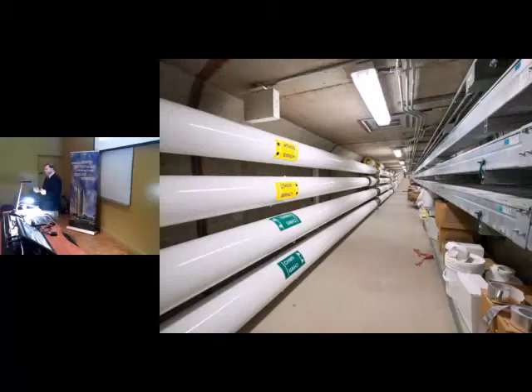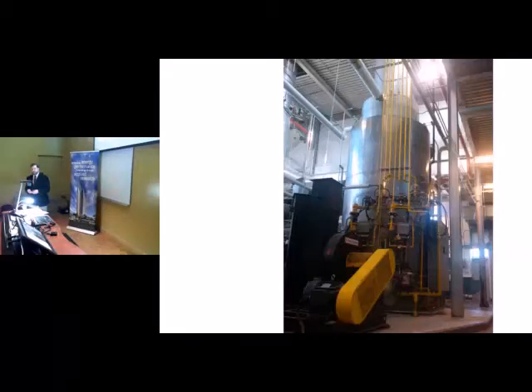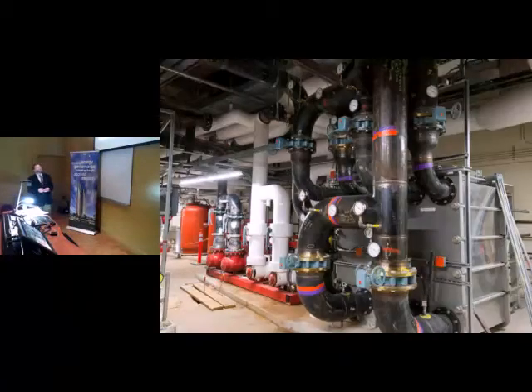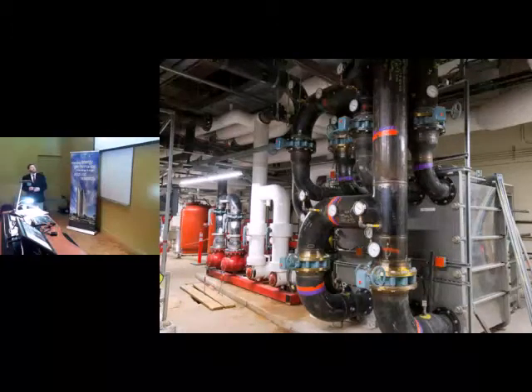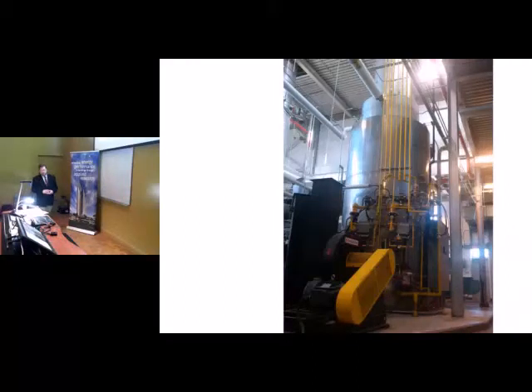We then take the water in the powerhouse and run it through an additional energy efficiency device, which is this device here. This is some of the heat exchangers in the basement of the air terminal building that deal with the various temperatures of water, I should say, and one of the main pumping stations. So some fairly hefty equipment that does all this work. But in the central utilities plant, we use a very unique device that is called, if I can find it here, flue gas condensing economizer.